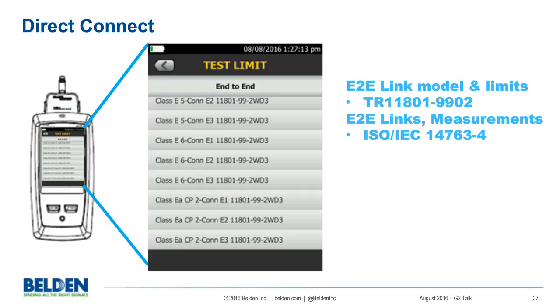There's different types of test limits, as shown on this graphic. There's several other screens on these testers with different numbers of connectors: 2, 5, 6, and so forth. Depending on the number of connectors in your channel, along with your direct connect at each end, you'd have to change to a different test limit. So the direct connect takes into account the number of connectors, yes, but it's not PL2 because it's not a permanent link.